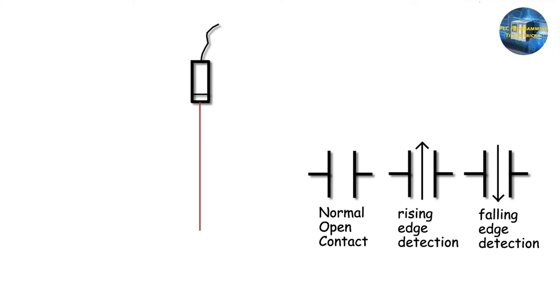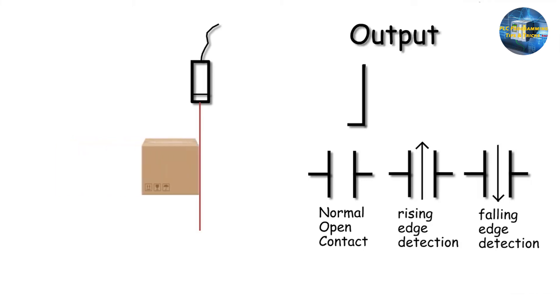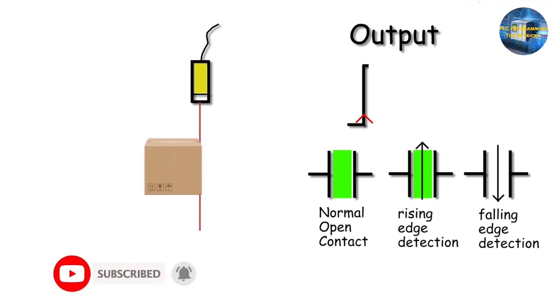Let's see an animation of how rising and falling edge detection works. The moment the front corner of the box is detected by the sensor, it gives an output signal and the normally open contact is closed. However, the rising edge detection contact will be turned on only for one PLC scan cycle — in the next scan cycle it is turned off.